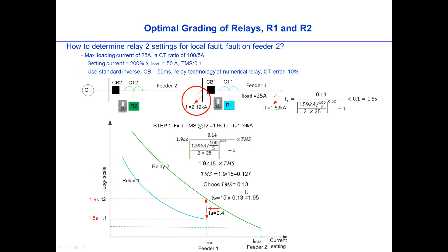What we can do is we can just calculate, if we choose this 0.13, then we can just do it here. So 15 times 0.13. Trip time. Because here, if we just look at this one, what we need is we need to update this value. So 15 times the new TMS. The TMS is 0.13. So now we have 1.13. No, the new trip time is 1.95. So now this time is updated with 1.95. It's adjusted.